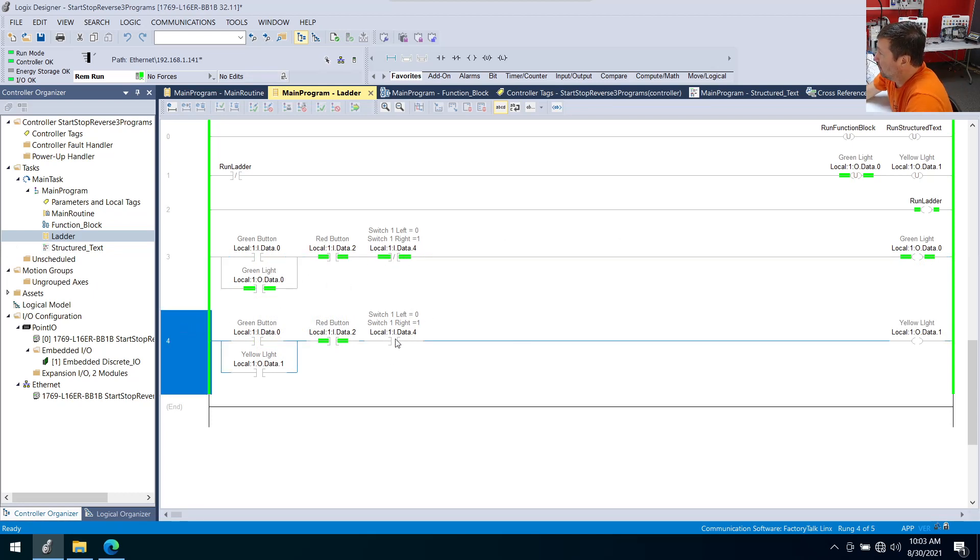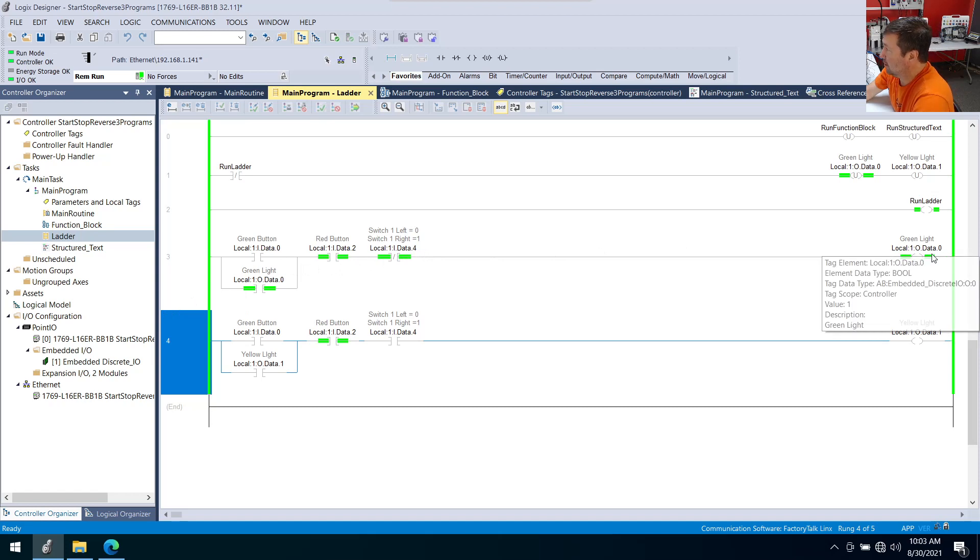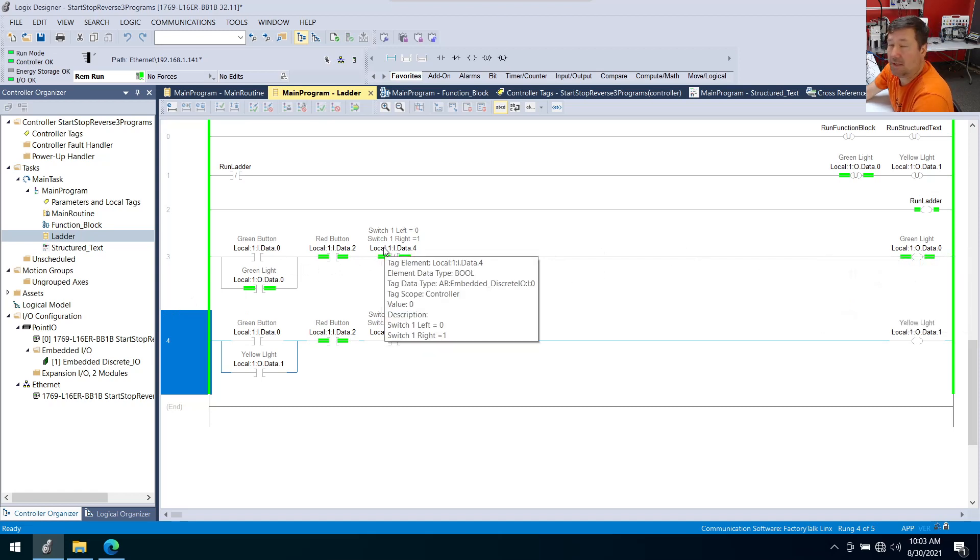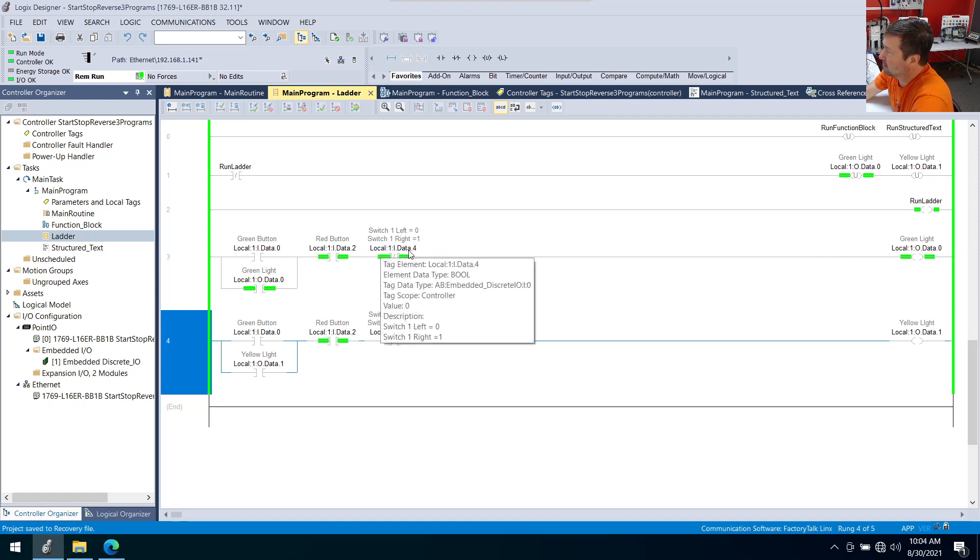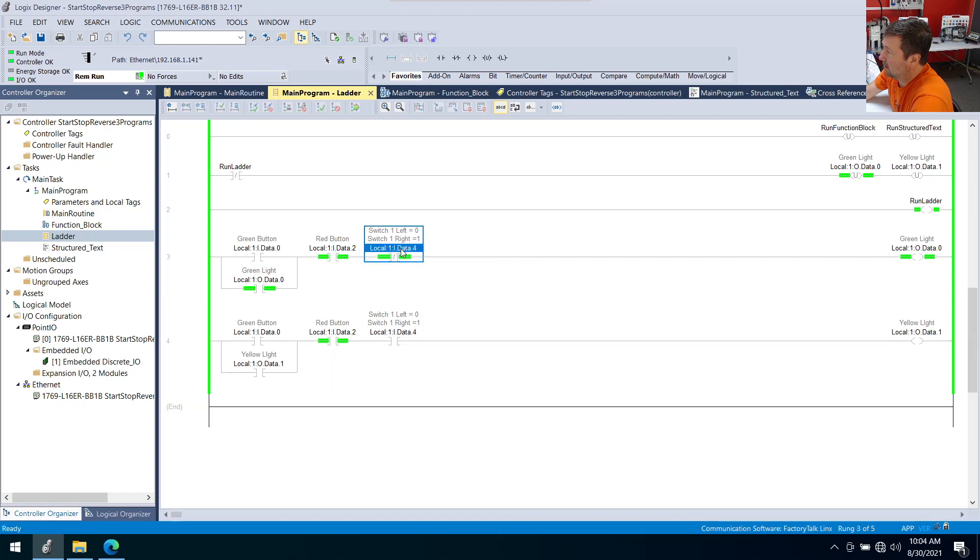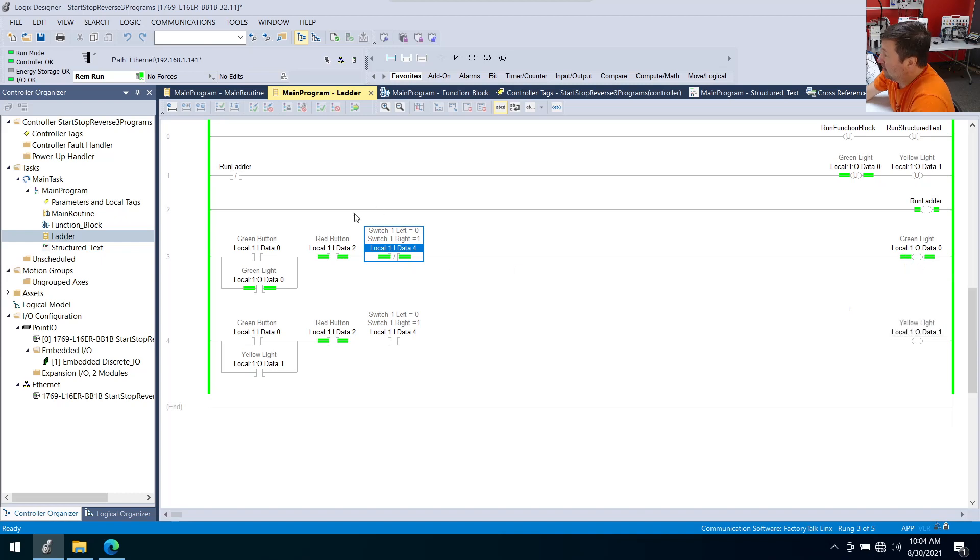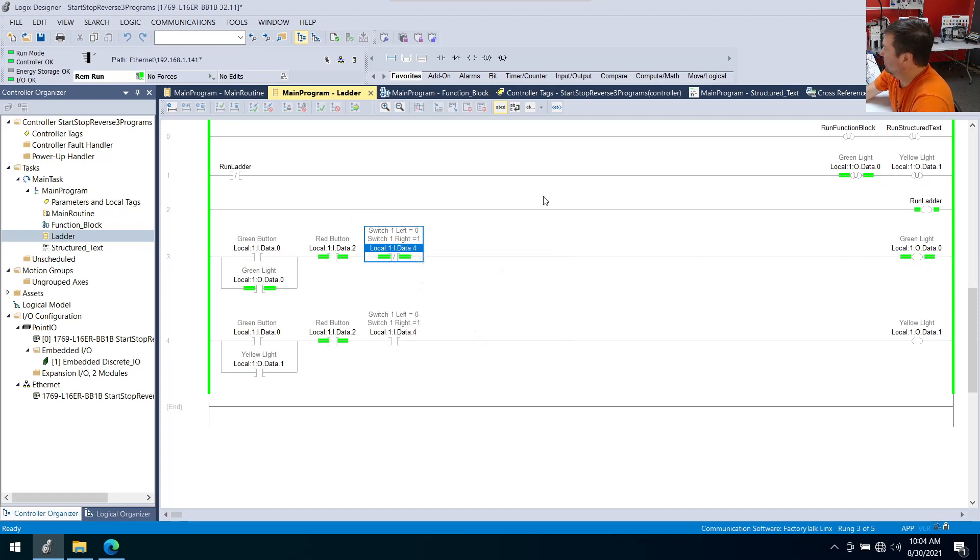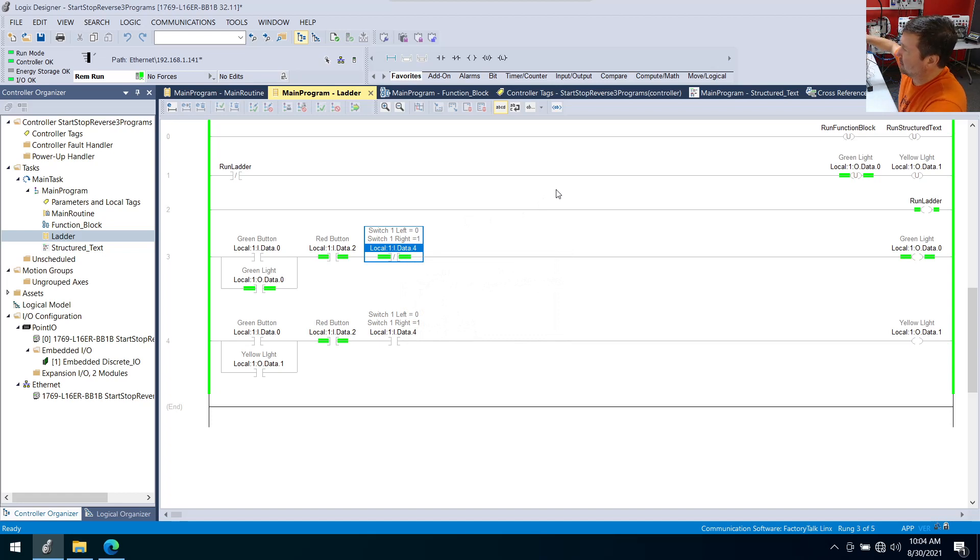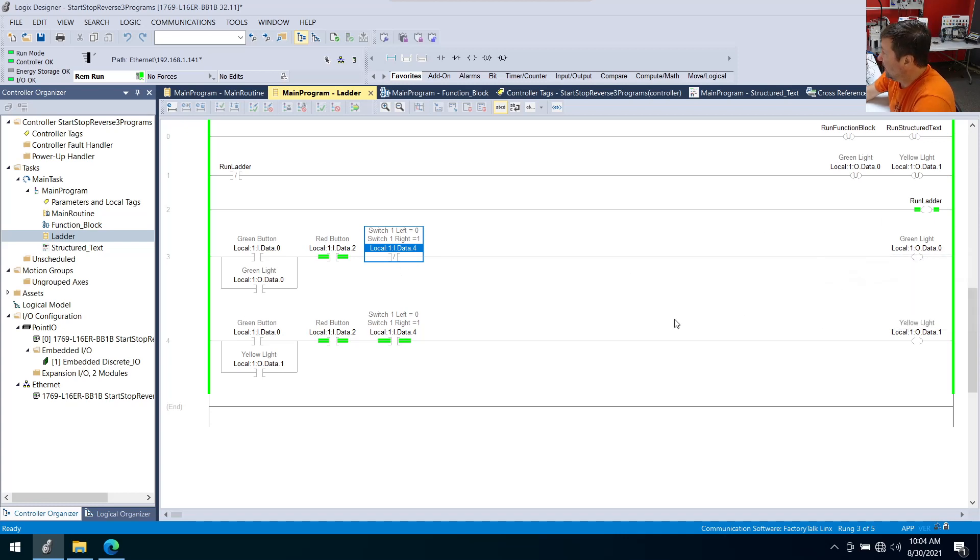And same on our yellow light. Right now it's waiting on switch one to be in the right position. Now notice I didn't have to add any special code in here when using the OTE to deal with switch one switching from the left to the right. Because the moment that I switch switch one to the right, we're going to have a one in input four. And this is going to be false. And that's going to drop out the green light. Now some of you did write this with the latch and unlatch. And so you struggled a little bit with getting this to turn off. You needed additional unlatch to deal with this. But when I switch switch one to the right position, this immediately becomes false. This writes a zero to our green light.